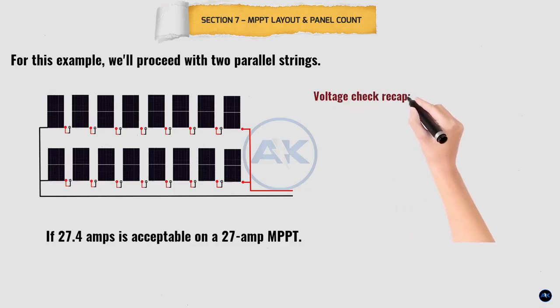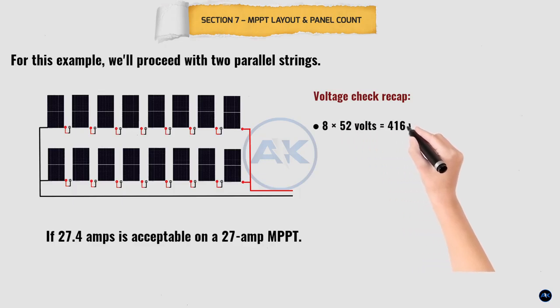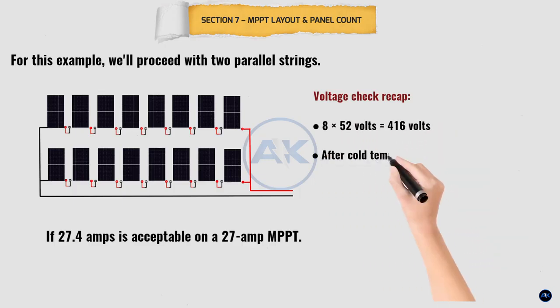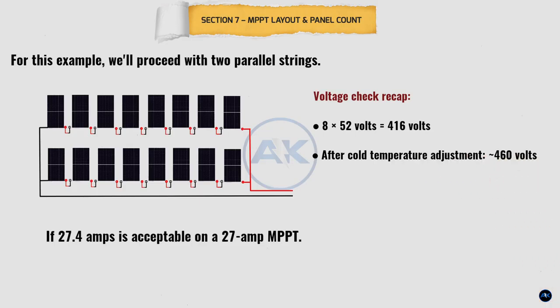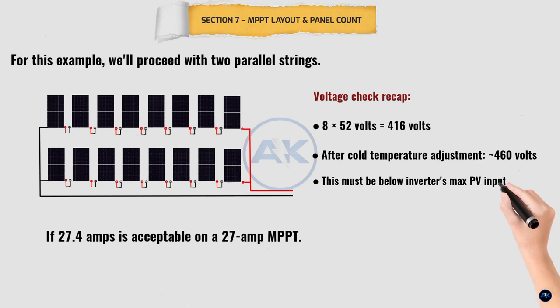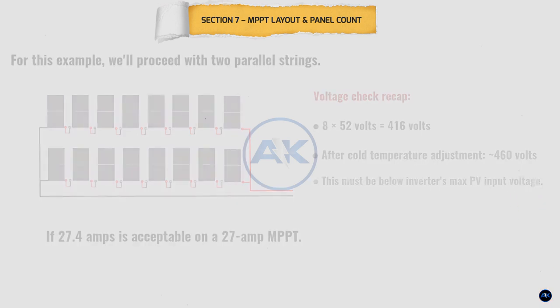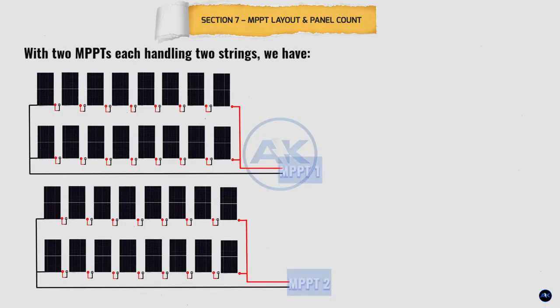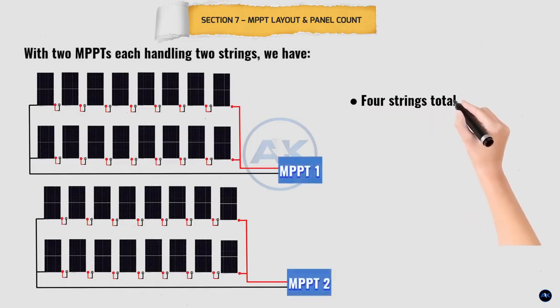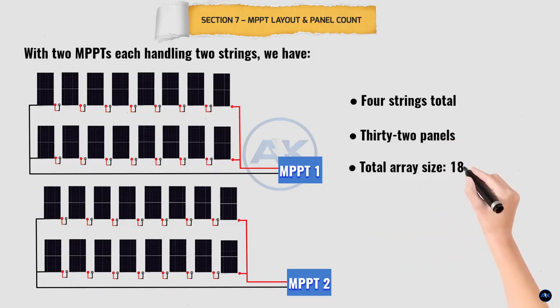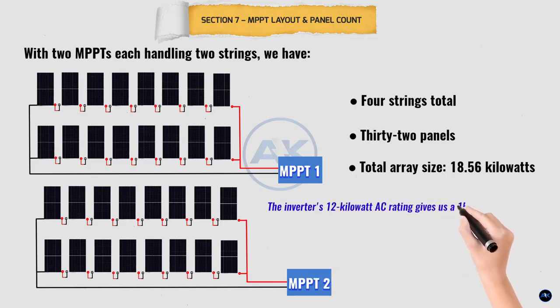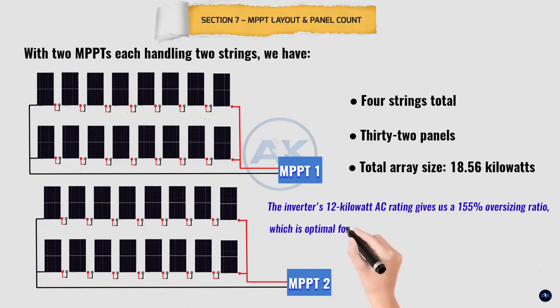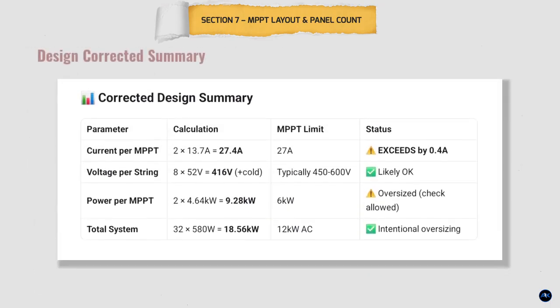Voltage check recap. 8 panels at 52 volts equals 416 volts. After cold temperature adjustment, about 460 volts. This must be below your inverter's maximum PV input voltage. With 2 MPPTs each handling 2 strings, we have 4 strings total, 32 panels, and total array size is 18.56 kilowatts. The inverter's 12 kilowatt AC rating gives us a 155% oversizing ratio, which is optimal for energy harvest, especially with battery storage. Design corrected summary.